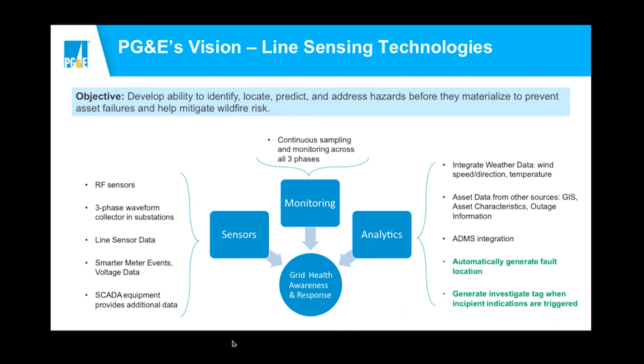In the next slide, I'll give a little double click on some of the core technologies I mentioned. First, the line sensor - our single phase conductor-mounted technology. The second is called EFD, early fault detection, an RF sensor we're piloting right now that's mounted right beneath the conductor. We're installing them on poles every 3 miles, and these sensors can coordinate with each other and triangulate disturbances on the line to pretty good accuracy.